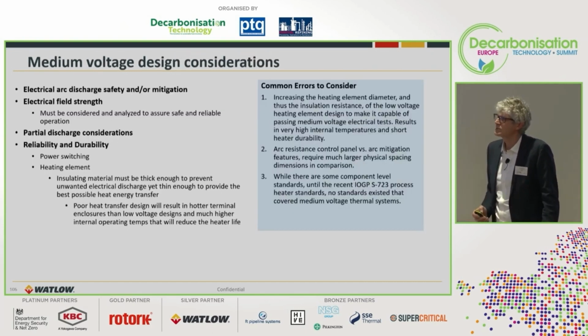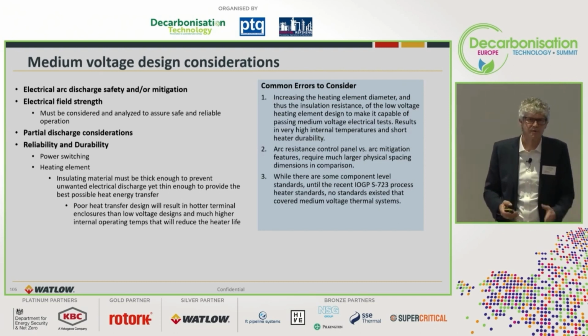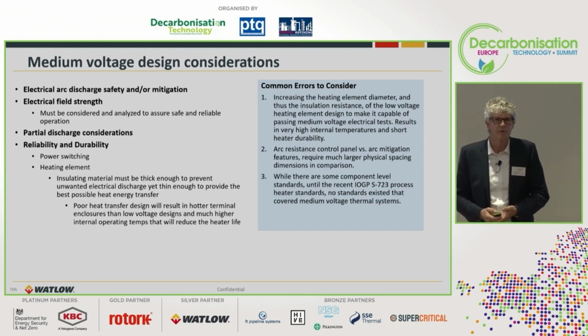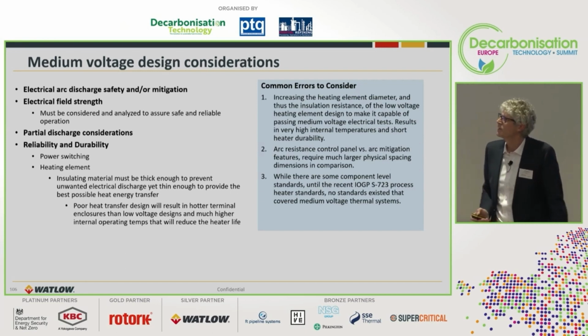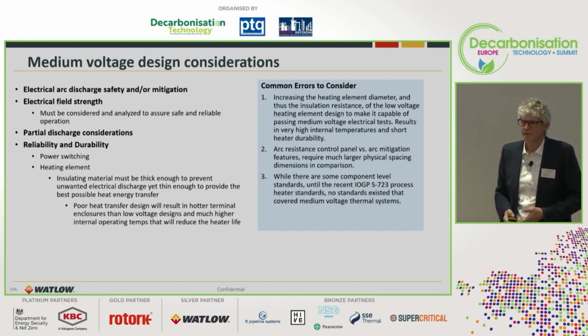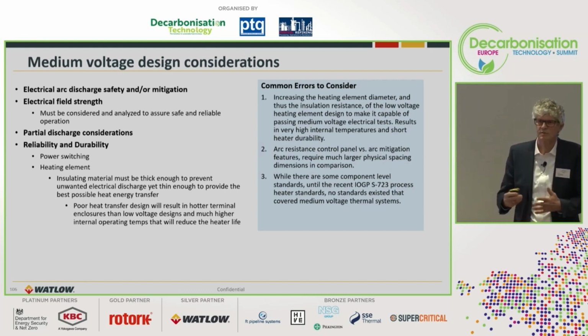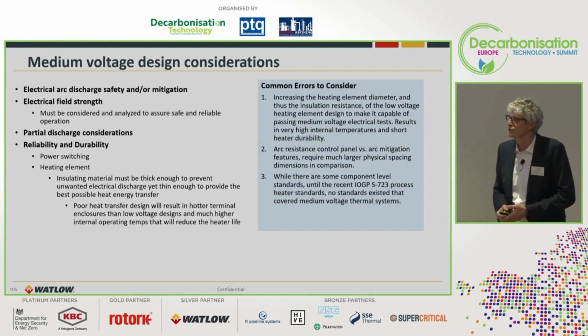There are certainly some things to consider when you have a medium voltage system or develop a medium voltage system, because of the much higher voltage. There are electrical risks like arcing. The electric field is much stronger. Partial discharge is more likely if you don't do it correctly.